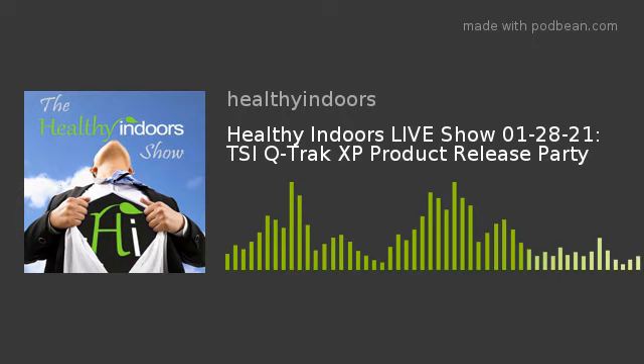Now, think about all the things that you do indoors. Let's just focus on commercial, not industrial, because confined space testing and intrinsic safety is a little bit different. But all this thing is, or anything, is basically a troubleshooting tool. So when you talk about ventilation, it's key to know what ventilation is. Your average person thinks, oh, that's the air that comes out of my air duct or my register. But ventilation in our world is clean, fresh air, outdoor ventilation, air that comes into the building, and then also air that exits or exhausts from the building.